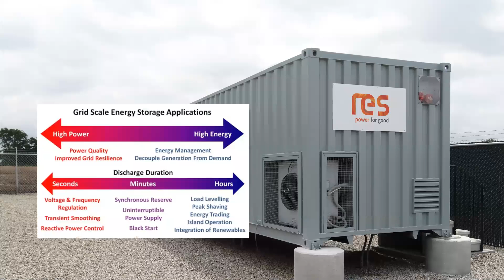As I mentioned before, some of the services a battery can offer to the grid go beyond just shaping a solar product or helping to manage load and supply. Some of the fast response capabilities of batteries allow you to offer ancillary services like reactive power compensation, frequency control and regulation, voltage control, all the way to longer duration things like backup and black start for conventional generation that would otherwise need significant diesel generation to restart after a shutdown.